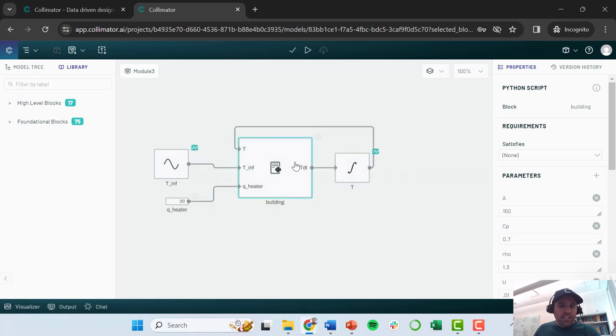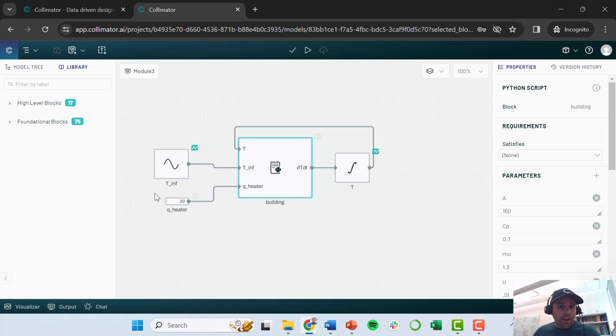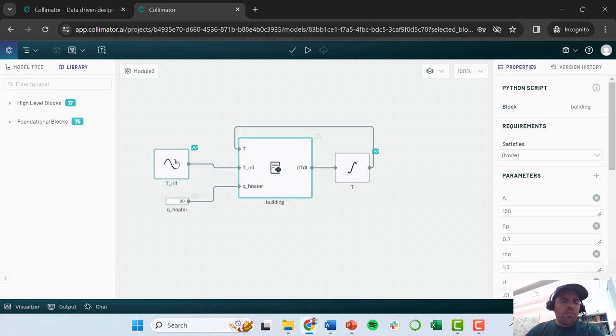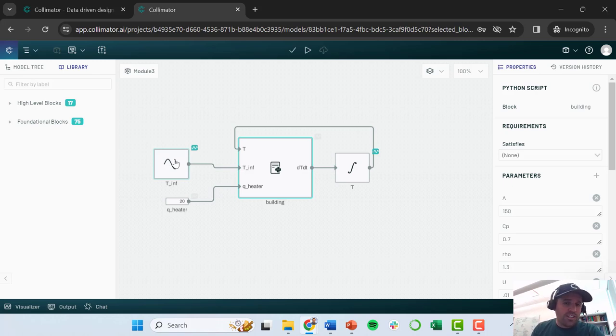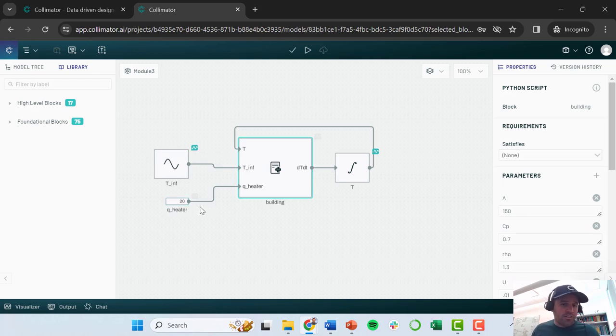We calculated dT/dt with our energy balance, integrated that temperature and fed it back into our model so that we could calculate temperature loss as a function of temperature inside the building. We gave our model external inputs, which this is the T infinity or ambient temperature. We modeled this as a sine wave. This is just a crude way of showing how weather might fluctuate outside over the course of a day. And then we also gave our model the ability to have this external heating value.